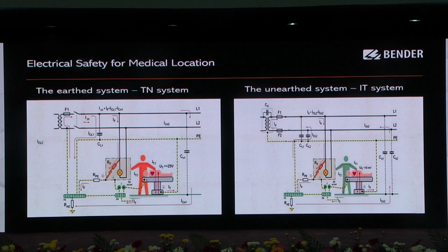So this is the standard. You can see the comparison of the TN system and IT system. The TN system can be used in group 0 and group 1, and the IT system can be used in group 2 locations.